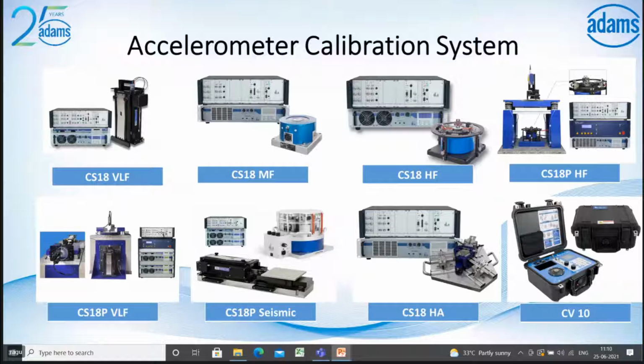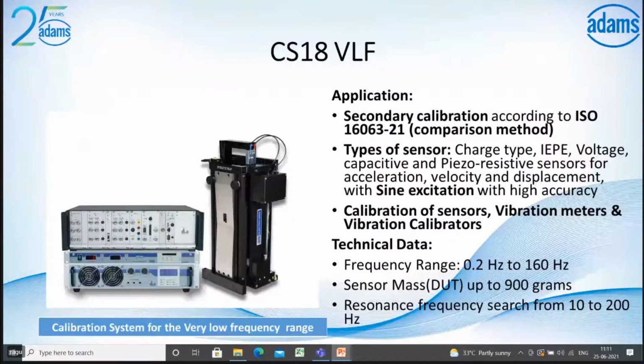So the CS18 VLF is the very low frequency system. It's a secondary calibration according to ISO standard 16063, and the calibration is done by the comparison method. What types of sensors can it calibrate? Charge type, ICP, voltage, DC and piezoresistive sensors, excited by a sinusoidal input. Apart from sensors, you can calibrate vibration meters and vibration calibrators from 0.2 Hz to 160 Hz. The maximum DUT mass is up to 900 grams, and resonant frequencies from 10 to 200 Hz can be handled.